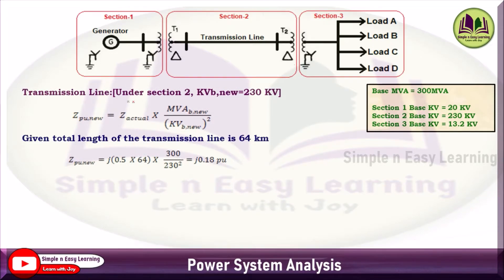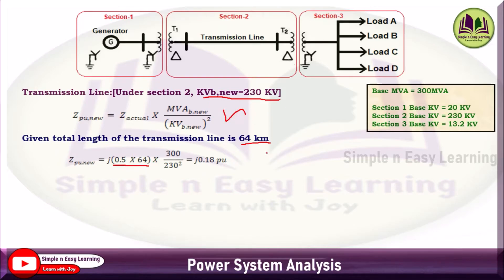The transmission line is in Section 2, so use base kV = 230 kV. The impedance is given in ohms: 0.5 ohms/km × 64 km. Since the impedance is in ohms, use: Z_pu = Z_actual × MVA_base / (kV_base)². Substituting: 0.5 × 64 × 300 / (230)² = j0.18 pu.